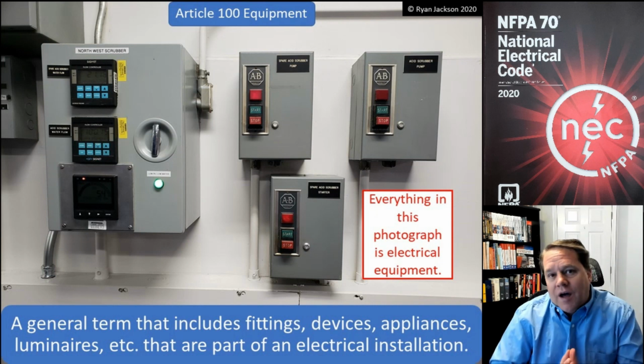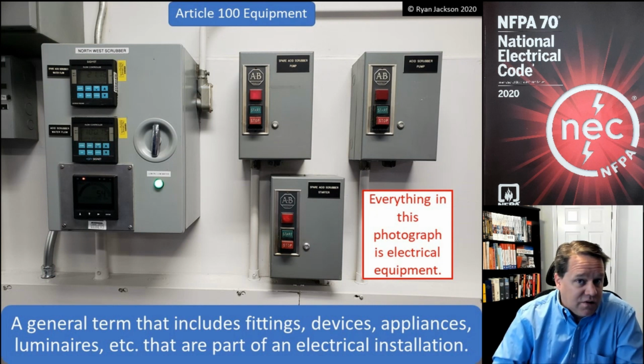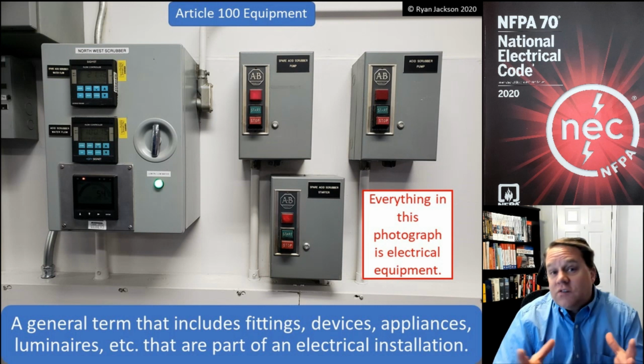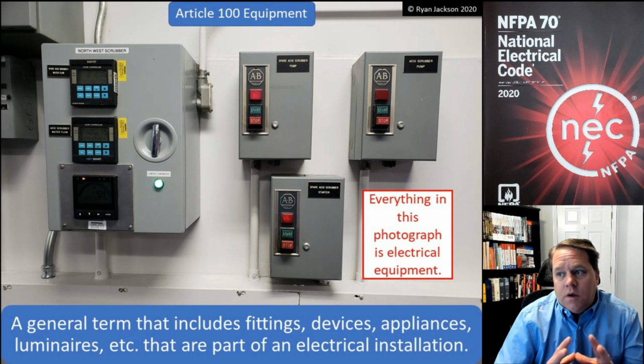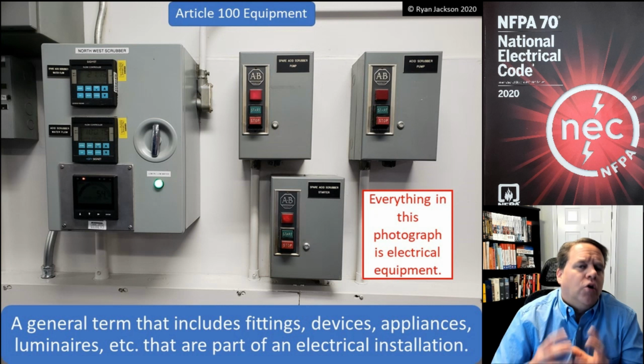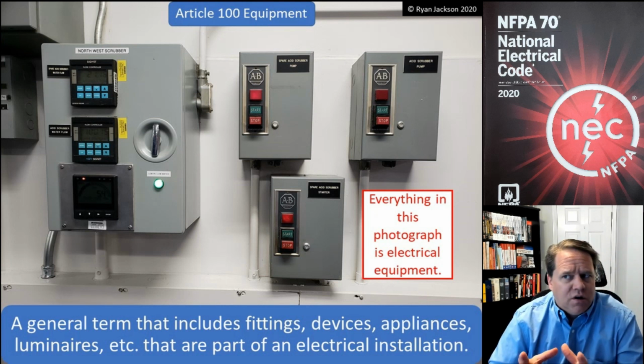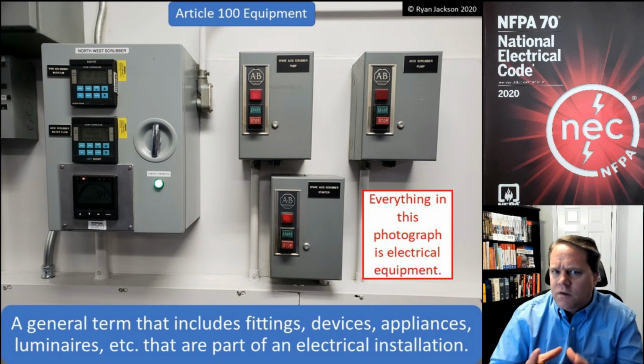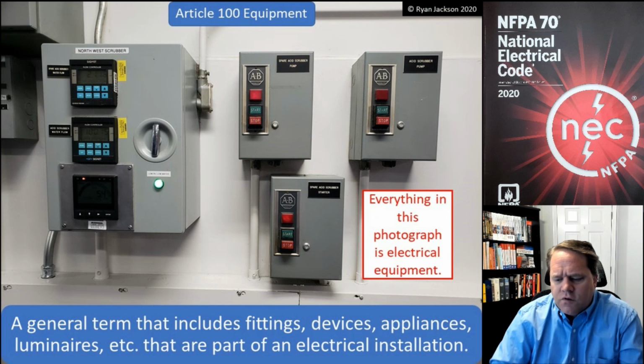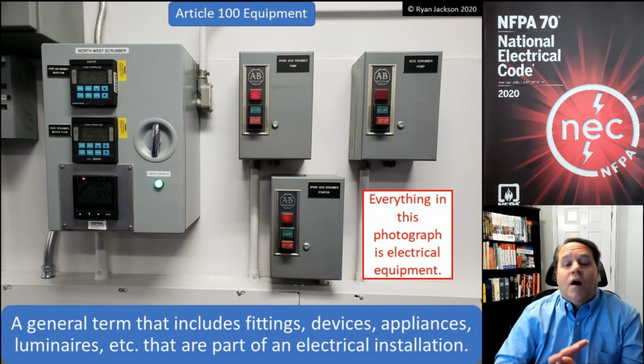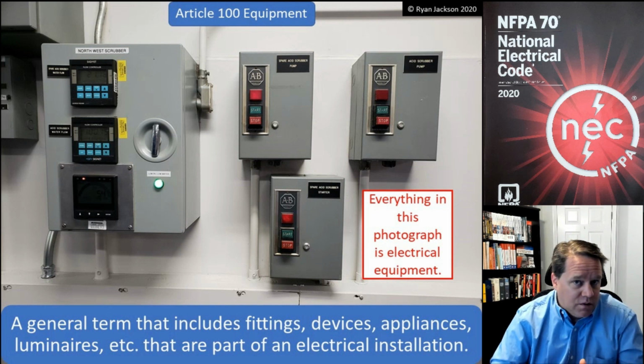Probably a better example is 110.26 that says access and working space must be provided and maintained about all electrical equipment in order to allow safe operation and access to the equipment. I paraphrase going off the top of my head, but it's very, very close to that. So you need to have enough space around all equipment to ensure that you can work on it safely.